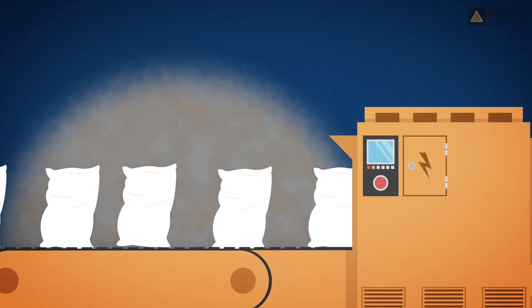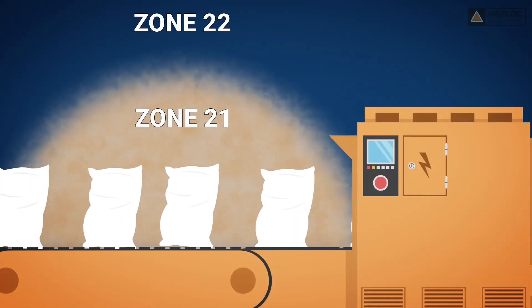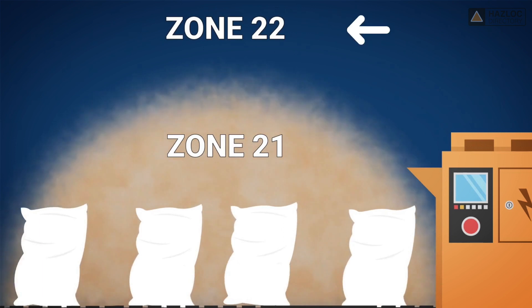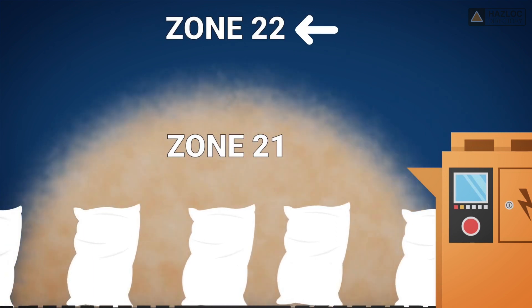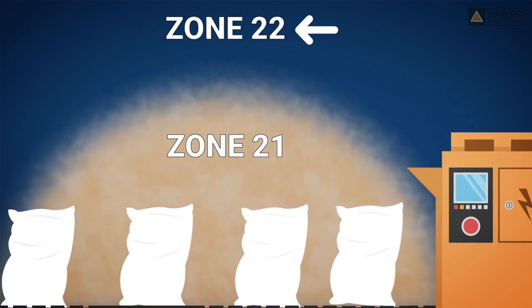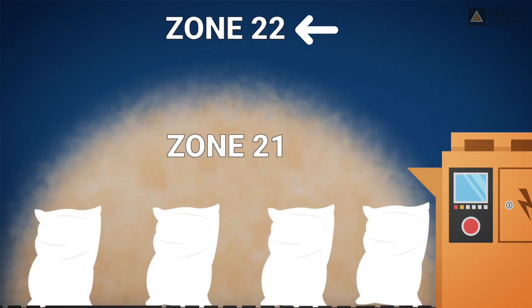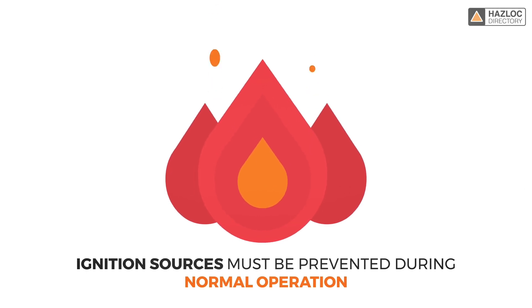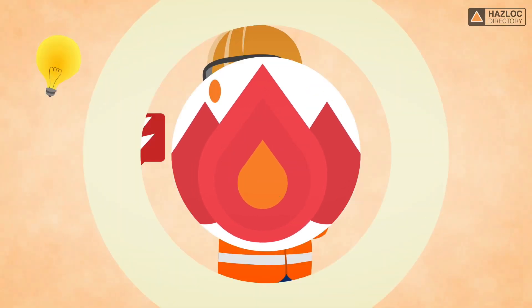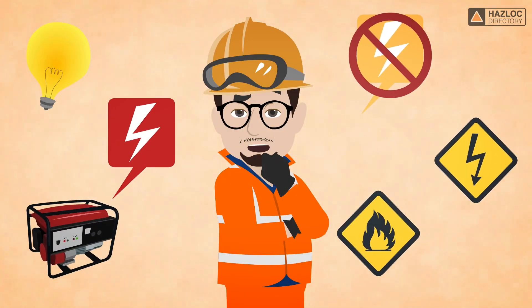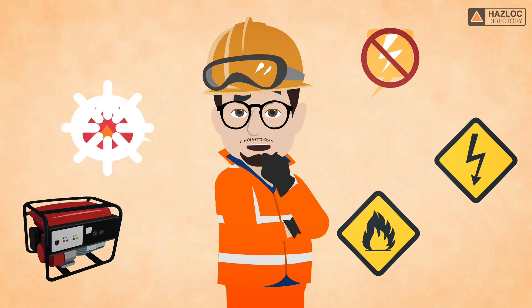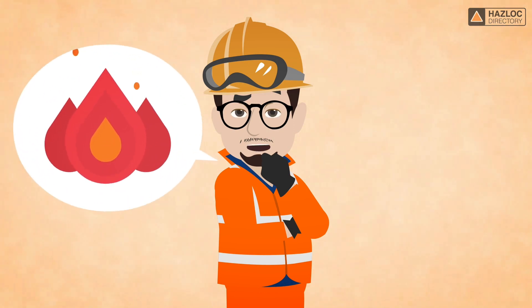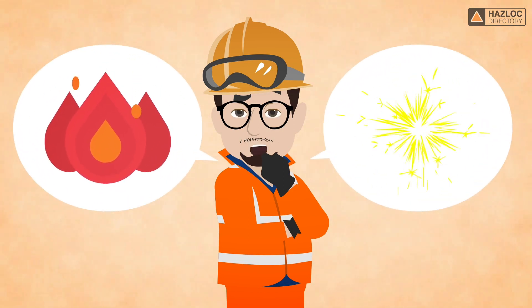Zone 22 is defined as an area in which an explosive dust atmosphere, in the form of a cloud of dust in the air, is not likely to occur in normal operation, but if it does occur, will persist for a short period only. Ignition sources must be prevented during normal operation. Electrical and non-electrical equipment used in Zone 22 must not become a source of ignition in the form of hot surfaces or sparks.